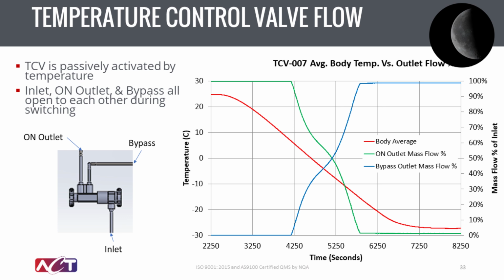So on this plot here, we have the thermal control valve. There's one inlet, and there's a bypass, and then what we call the primary on outlet. The red line across the center is the body average temperature. And as that temperature crosses below 10 degrees C, we can see that the flow then switches from primarily being the on outlet mass flow over to a roughly 50-50 mix around 5,250 seconds. And then as the temperature continues to drop and gets below negative 10, it is now in full bypass mode.